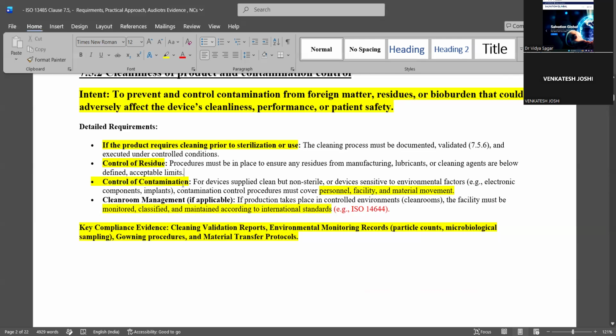Okay, the third is control of contamination. This applies to devices supplied clean but not sterile. See here, the first point we discussed was about sterile products, but there will be some non-sterile products, and still you have to supply them clean, because just because they are non-sterile, you can't supply them as you like. So for them, you need to use contamination control, for non-sterile devices or devices sensitive to environmental factors, like electronic components and implants. The contamination control procedure must cover personnel, facility, and material movement. So for those you are providing non-sterile also, you see that there won't be any particulate matter and there is less bioburden. Okay, you can't make it zero because you are not sterilizing them.